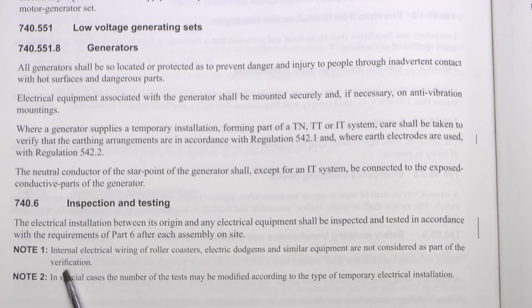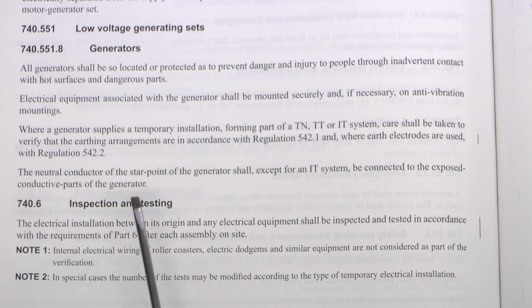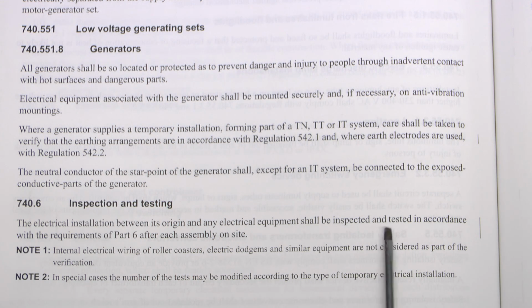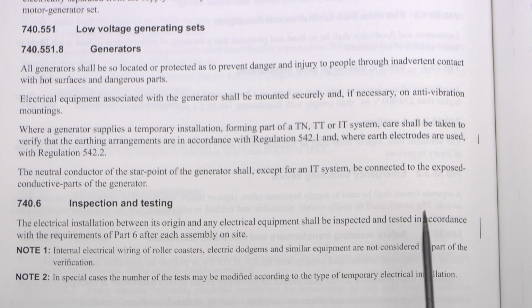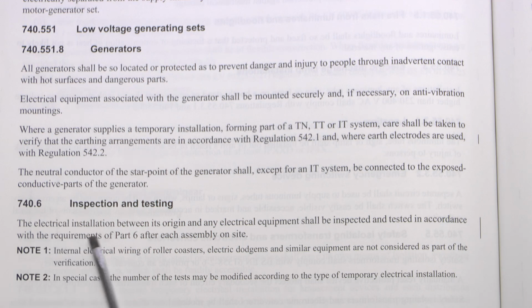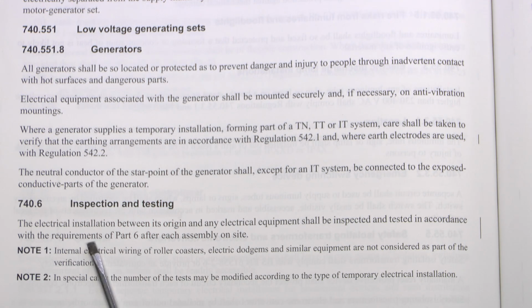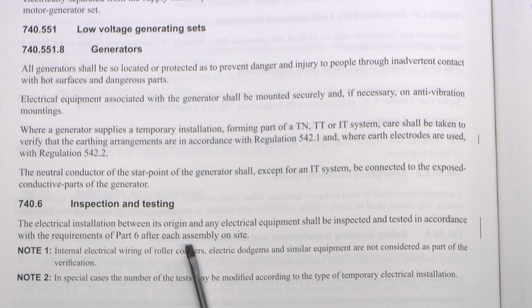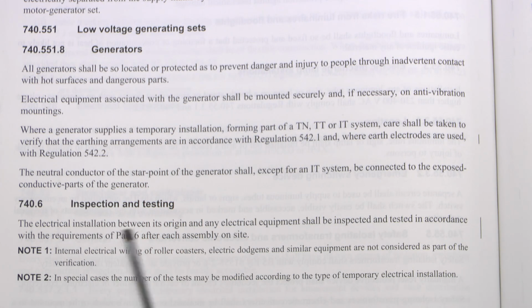And the other change in this section, 740.6, inspection and testing, we've now got a new part which starts here. So it's electrical installation between its origin and any electrical equipment shall be inspected. That's where it used to end. Now we've got and tested in accordance with the requirements of Part 6 after each assembly on site. So it now refers specifically to the procedures in Part 6, which are the standard inspection and testing procedures, whereas previously it was just that it should be inspected and tested.